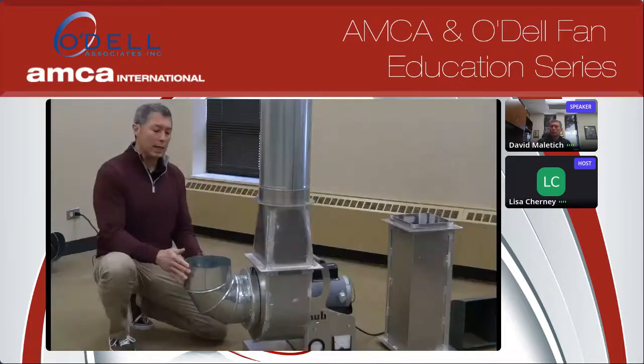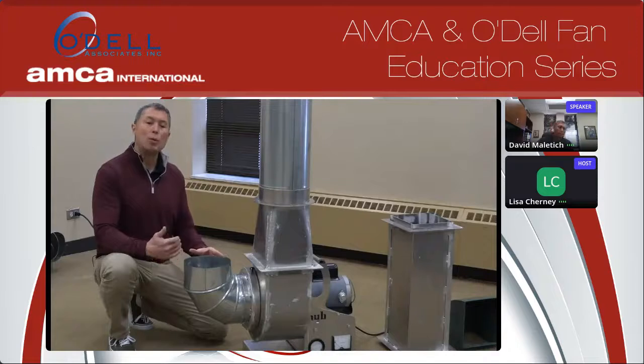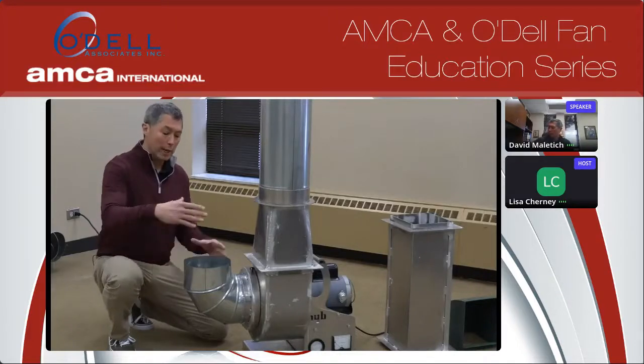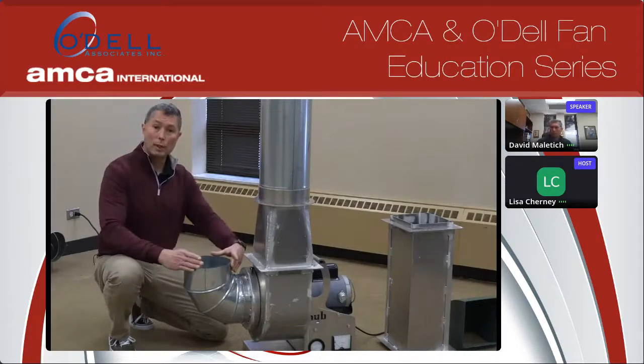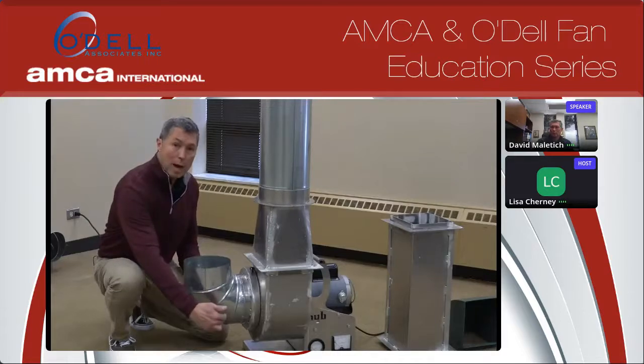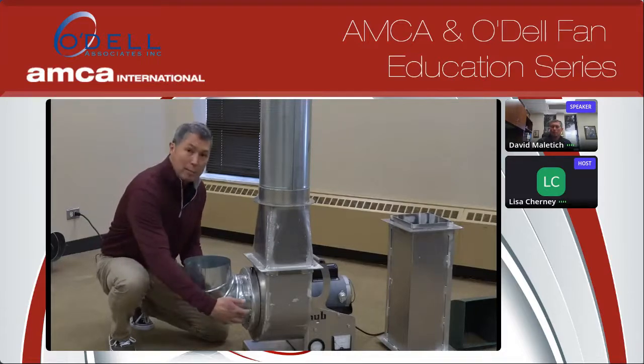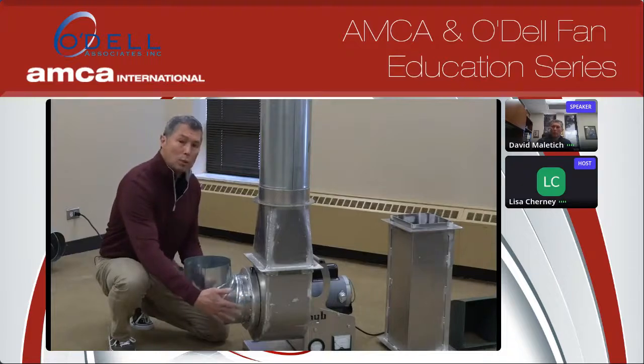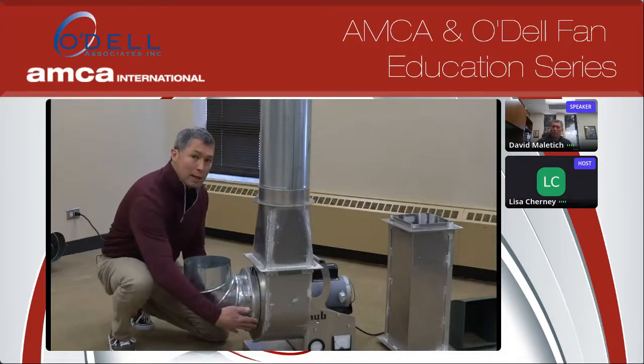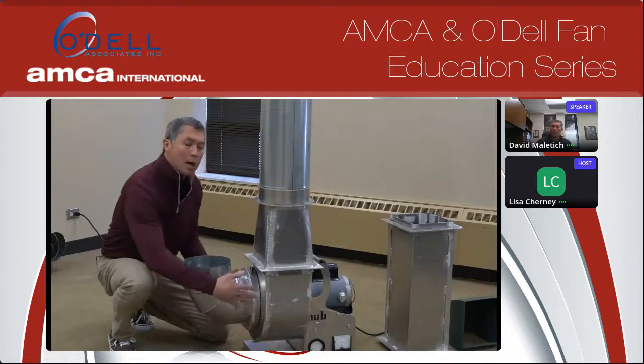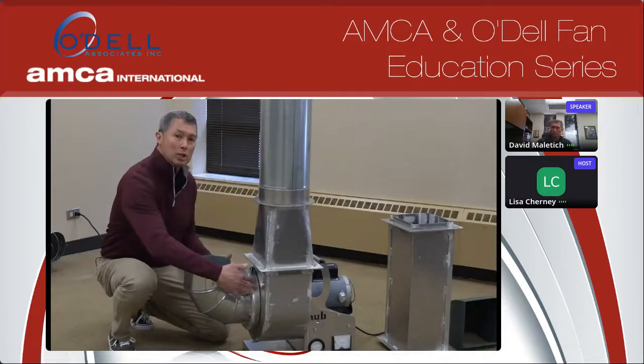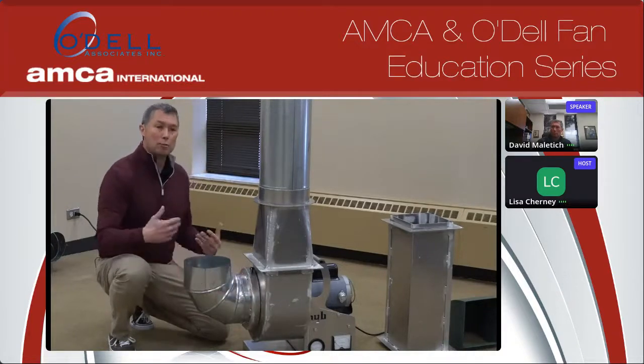What's happening is air has mass, and when anything has a mass to it, it wants to go in a straight line. So the air enters this duct uniformly, it wants to go straight down to the bottom, and then it has to bend 90 degrees into the fan. So basically what we're doing is we're loading the bottom half of the fan wheel as it's rotating, but the top half of the fan wheel doesn't get any air, so we're not fully utilizing the mechanical aspects of this fan.